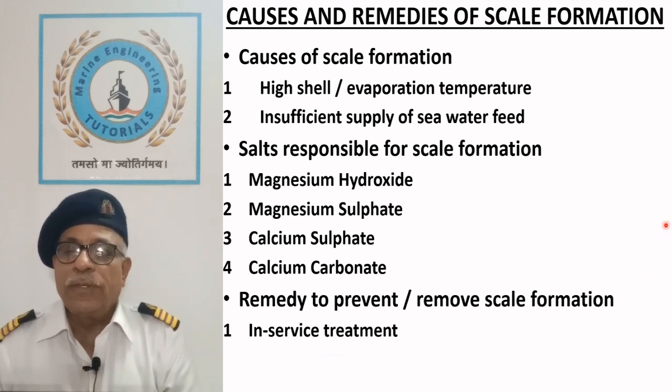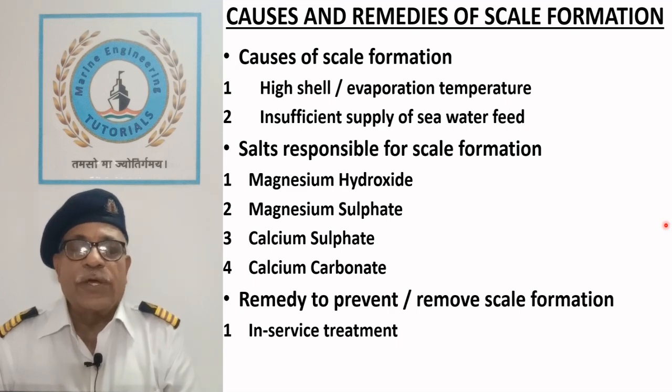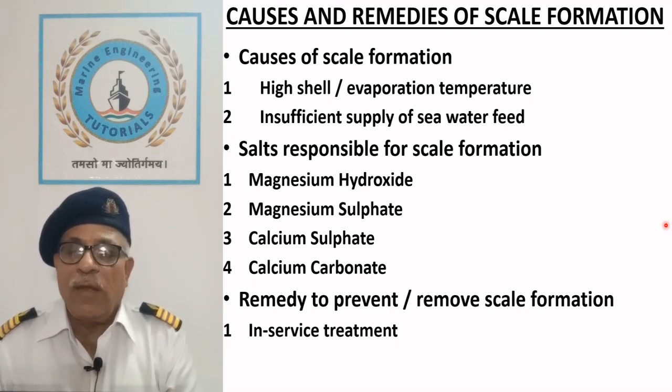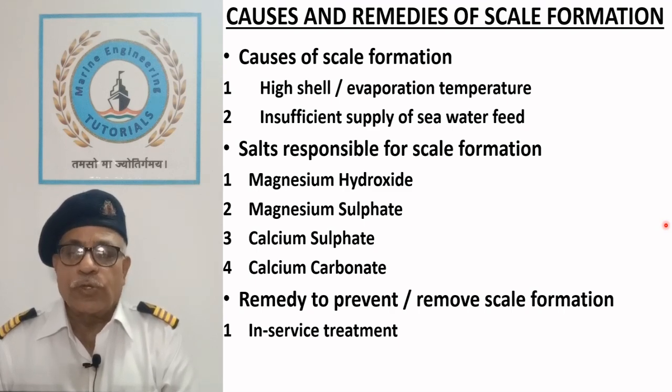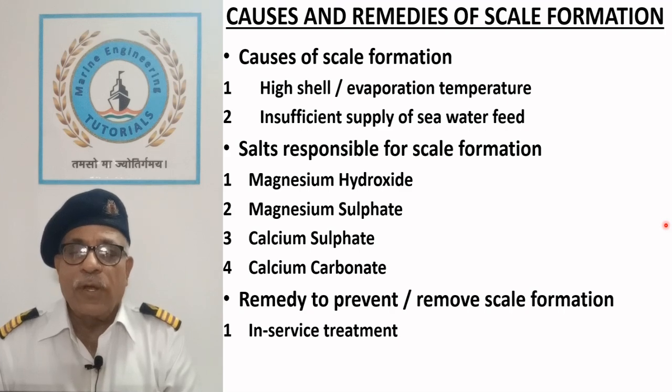Scale inhibitors used during the service interfere with the crystallization process of these salts with scale forming salts. Some chemicals bind the scale forming ions in the solution and prevent their deposition. Scale dispersants used disperse the small particles and prevent their deposition.